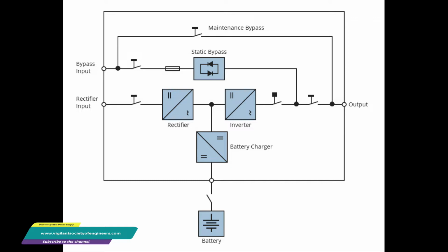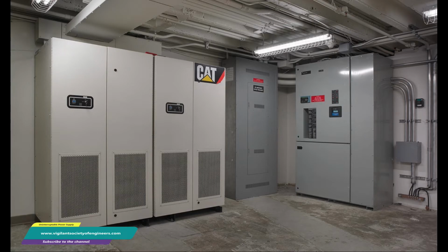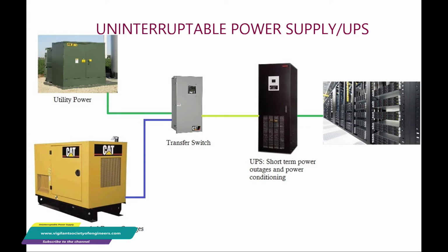Now the static switch. This circuit is a relay, more commonly achieved by using a thyristor, a key UPS component. Importantly, its purpose is to switch the load between the inverter and the utility supply. At all times, the output of the inverter is in phase with the utility main supply. Therefore, any switching between the two will be virtually seamless. This arrangement ensures that if the inverter experiences an overload condition, the circuit will transfer the load to the more resilient main supply.